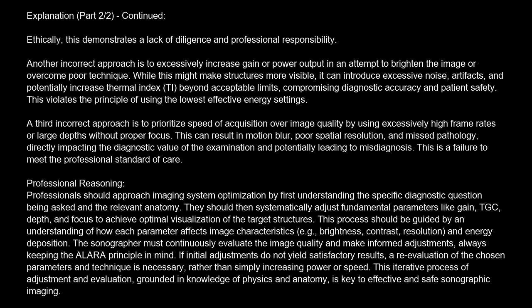Another incorrect approach is to excessively increase gain or power output in an attempt to brighten the image or overcome poor technique. While this might make structures more visible, it can introduce excessive noise, artifacts, and potentially increase thermal index (TI) beyond acceptable limits, compromising diagnostic accuracy and patient safety. This violates the principle of using the lowest effective energy settings.